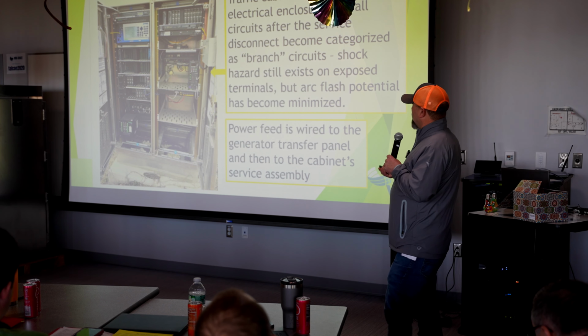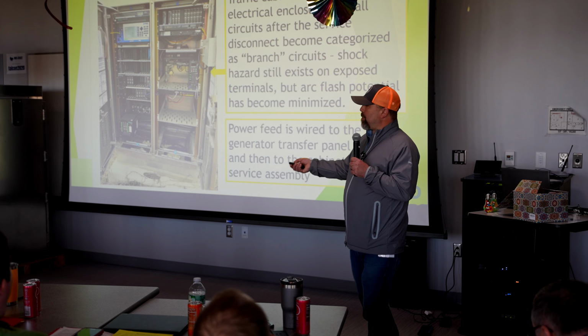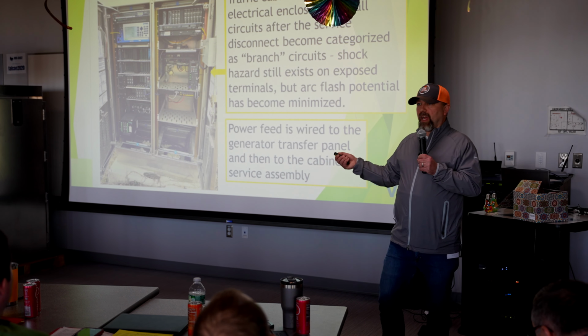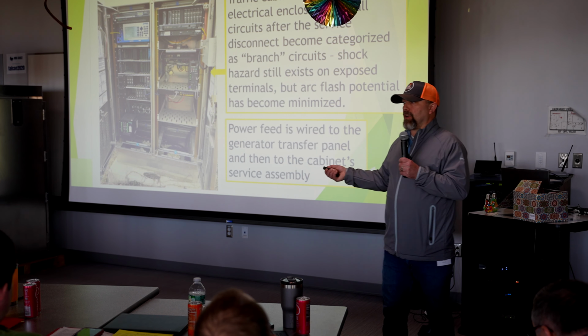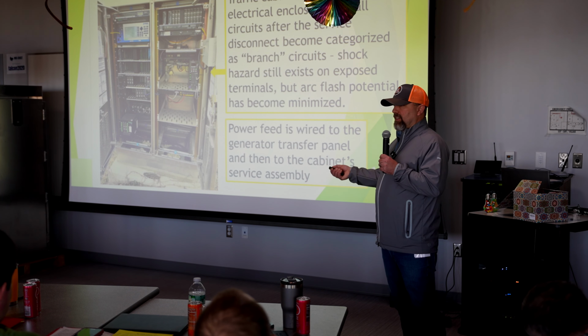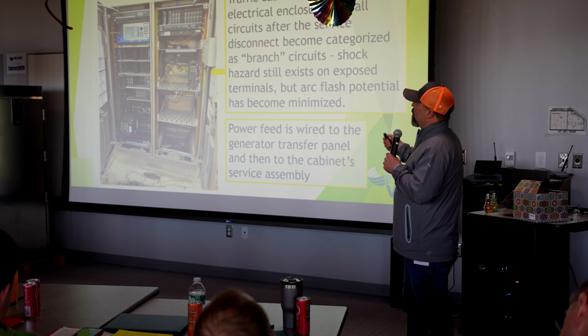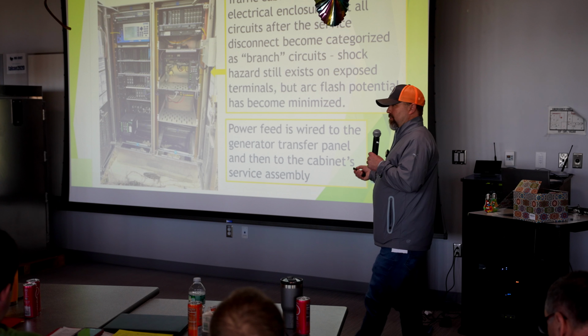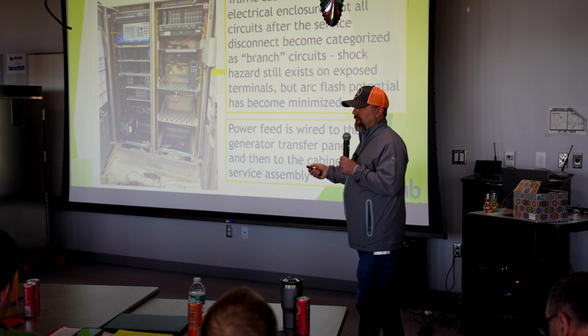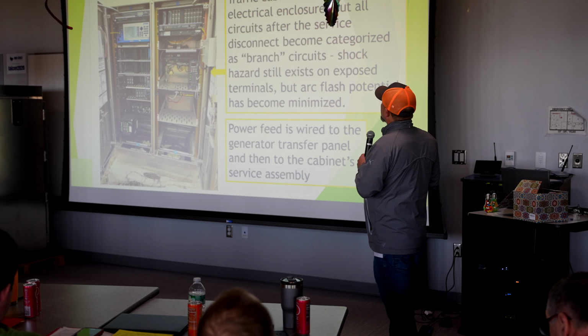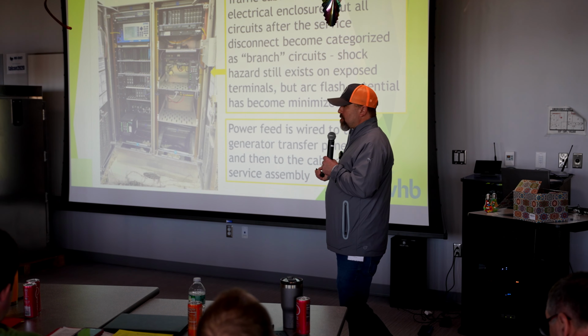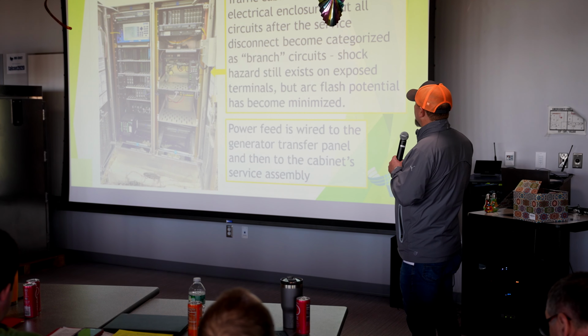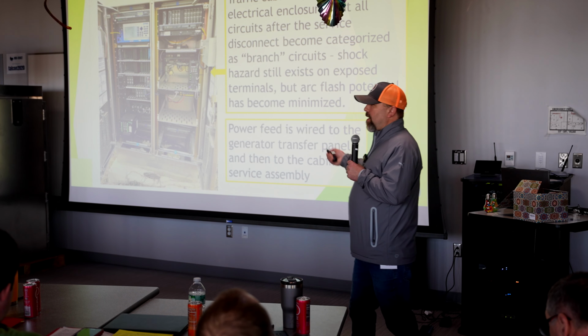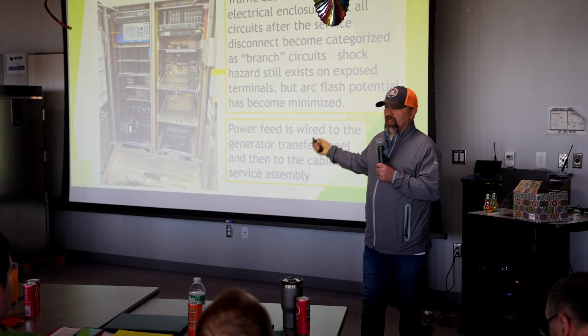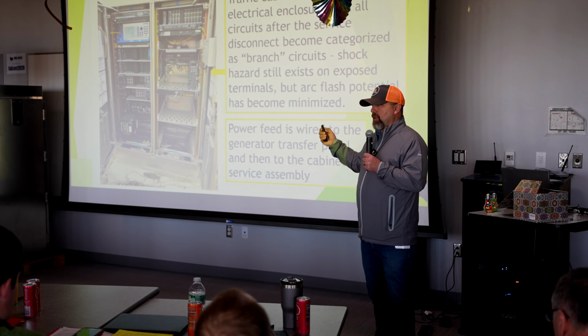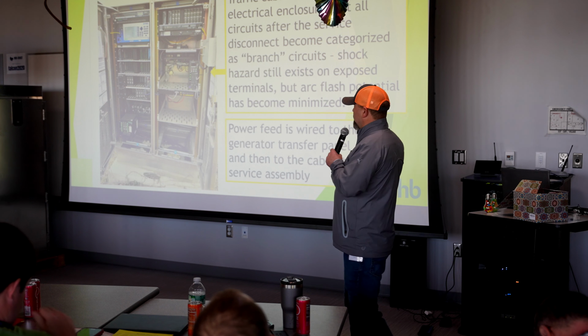So just to touch on what I said earlier, these cabinets, by and large, are rated as NEMA enclosures, so they are an electrical enclosure. The circuitry that resides inside of it is pretty much considered branch circuits. There's still a shock hazard present with them, but because we now have a service disconnect on the outside, you're not so much exposed to arc flash potential.